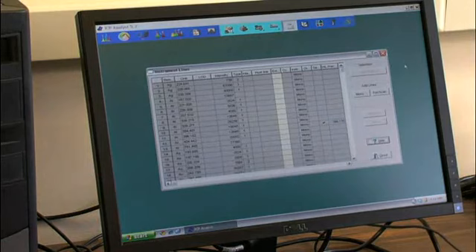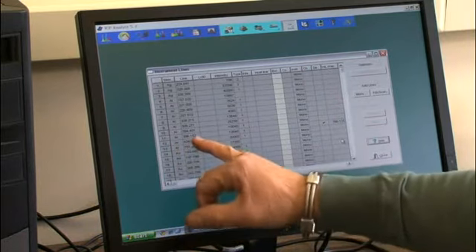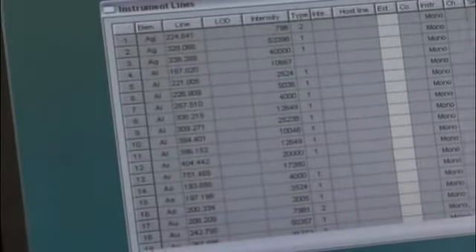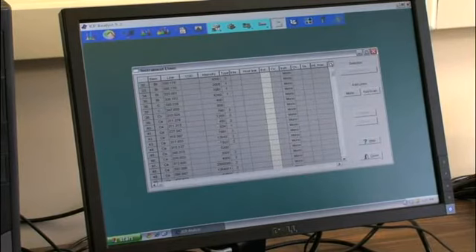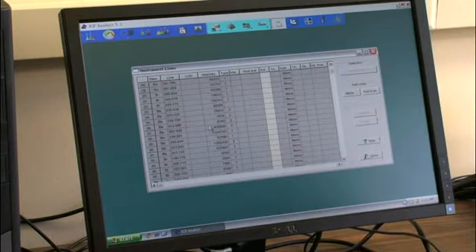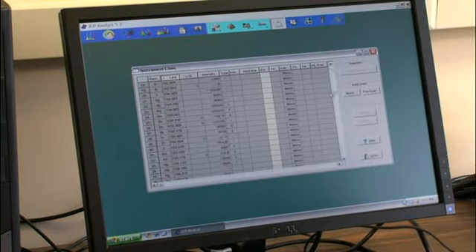This is a library of all your wavelengths. The ones that have an offset, this is supposed to be wavelength practical, which means that I've used this aluminum line and it found it at, this is the theoretical and this is where it actually found it. So if for some reason you need to take the offset out, then it'll go back and look for that wavelength at the theoretical position. This intensity column will tell you the detection limits, the ones with the, where's barium 455? That's not here. Some of these are not in here. I don't know why, but if you click on this and make them all numerical, then they'll come up. But I wanted to see what barium 455 was at.